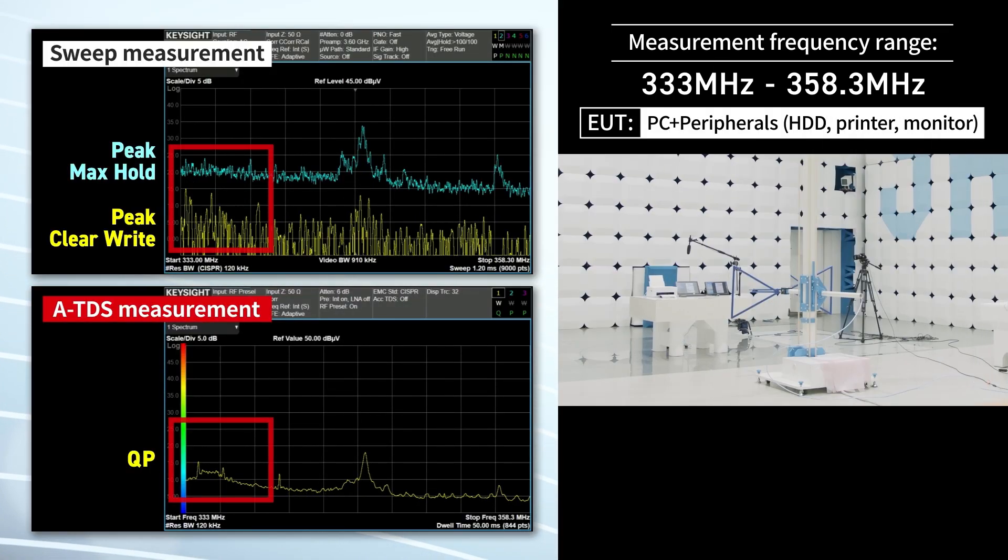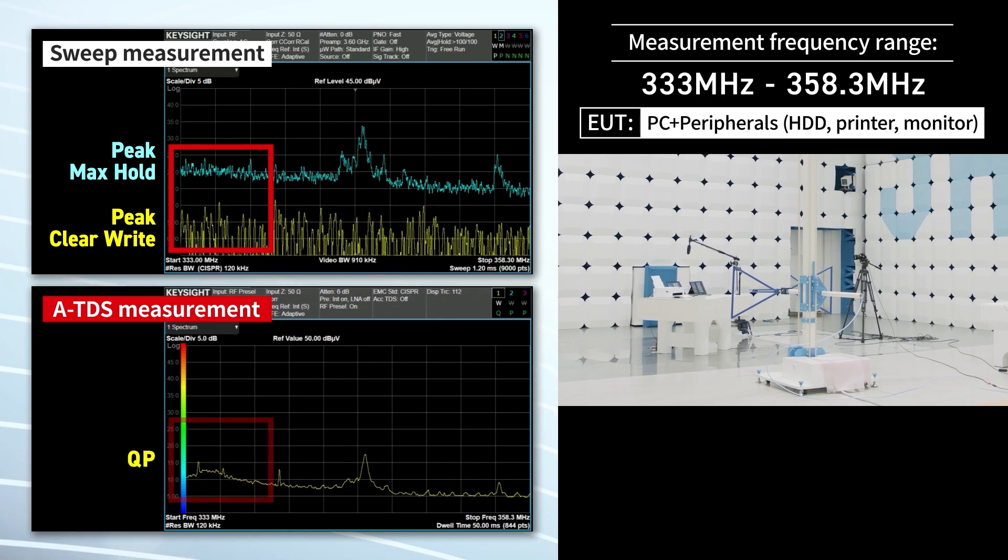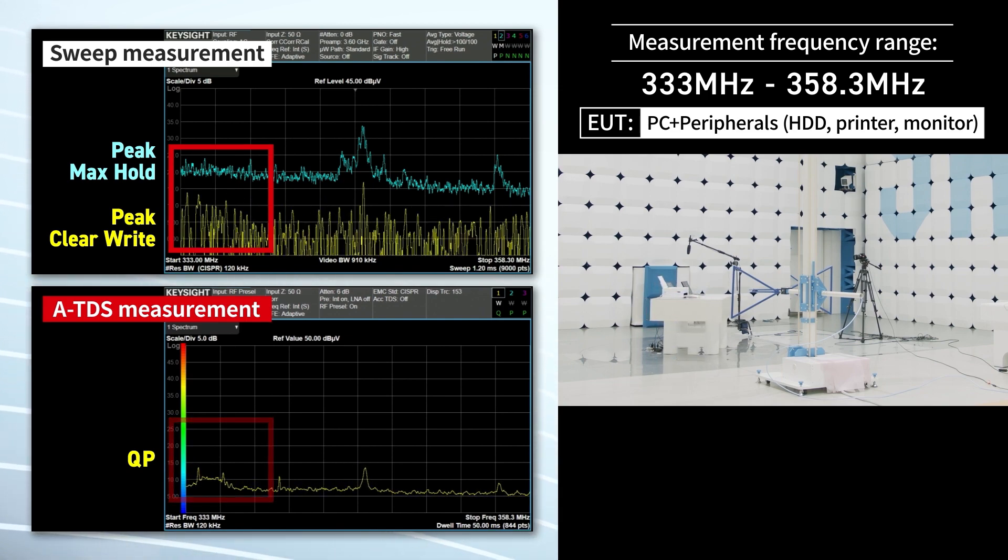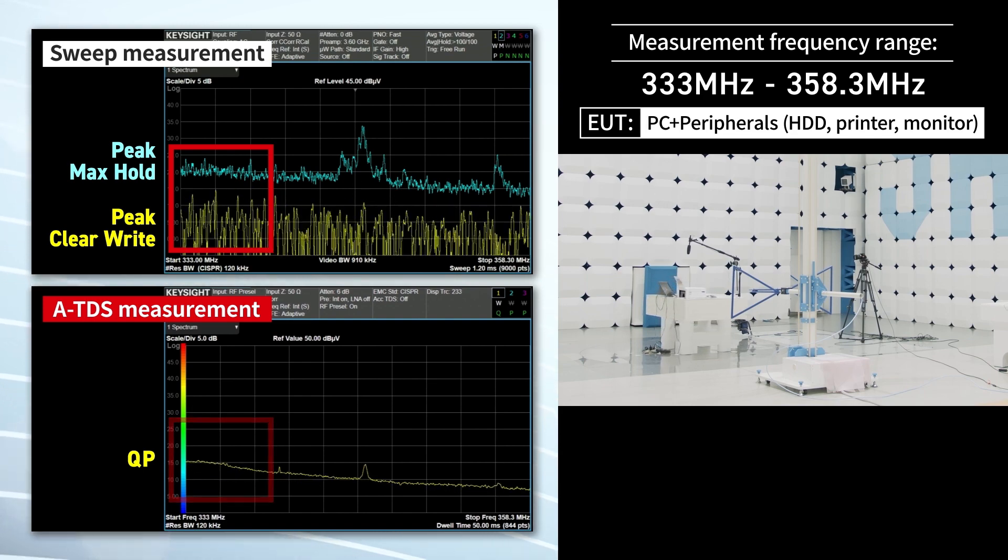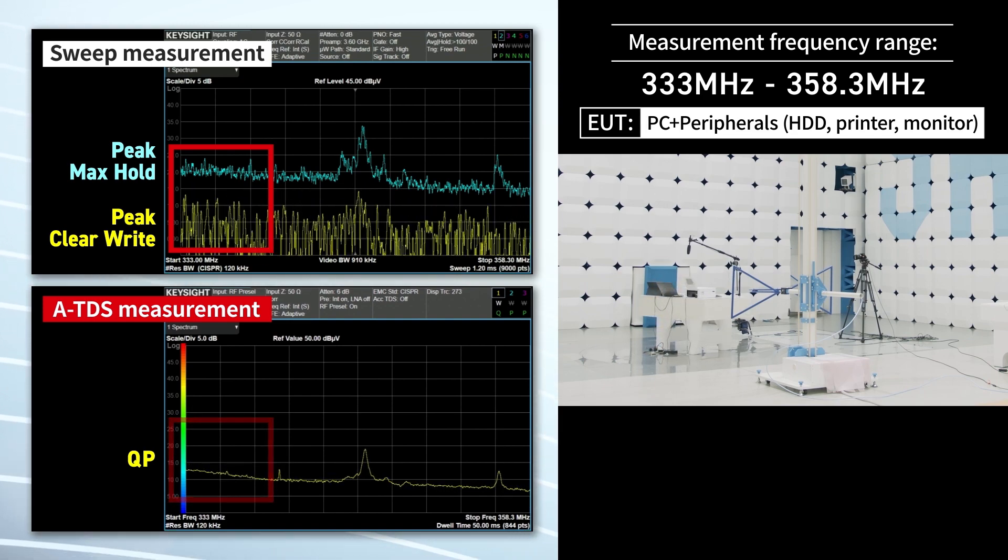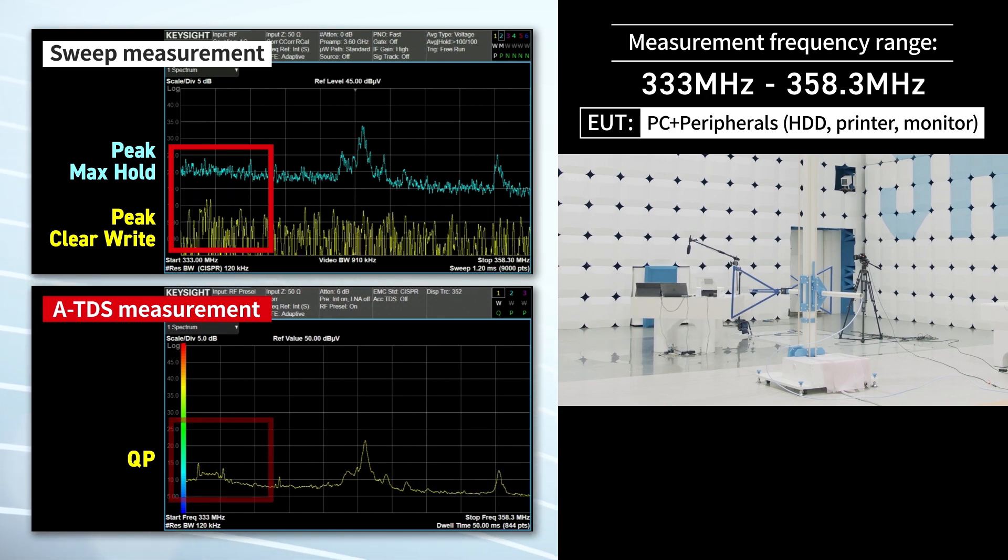Now, let's look at the noise behavior at another frequency range. During ATDS measurement, you can see spread spectrum-like noise on the left. It continuously varies with the rotation of the turntable. You can obtain accurate results even for situations like this.